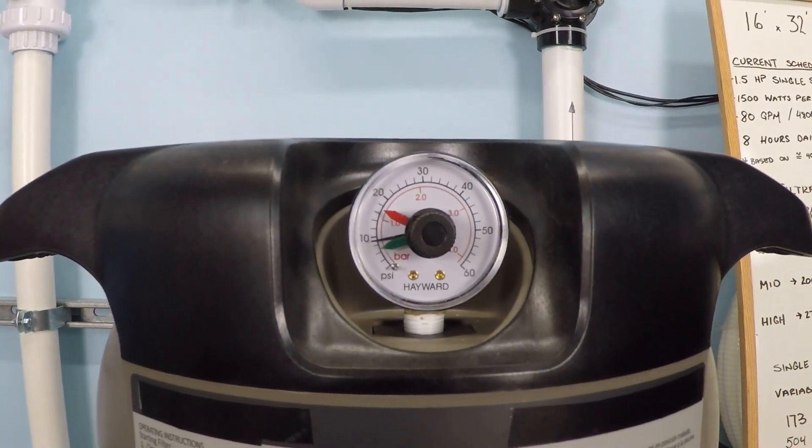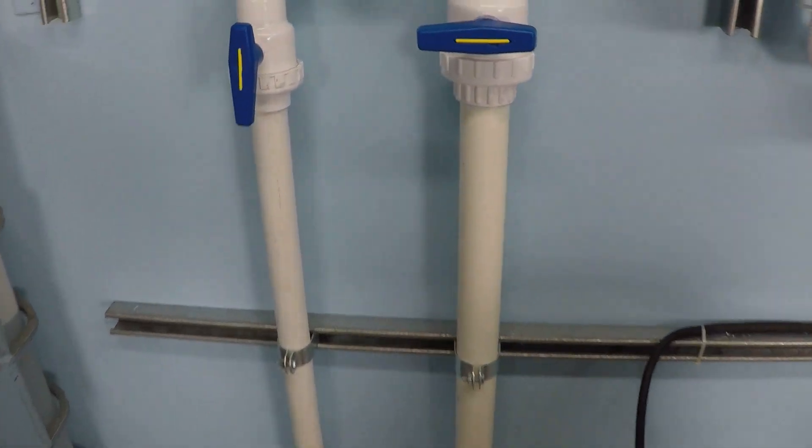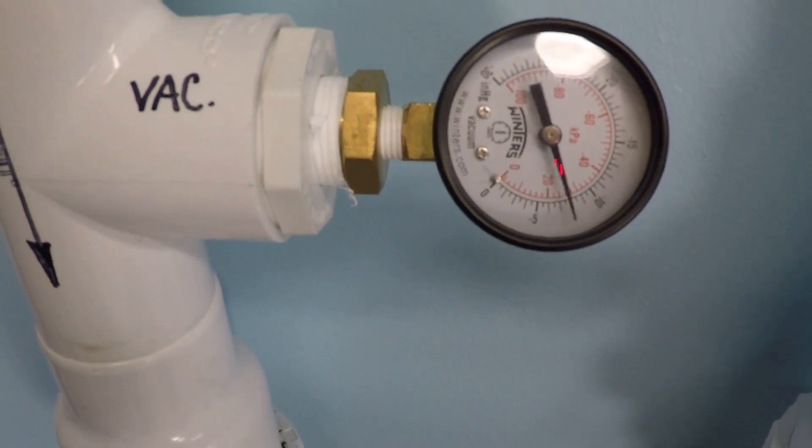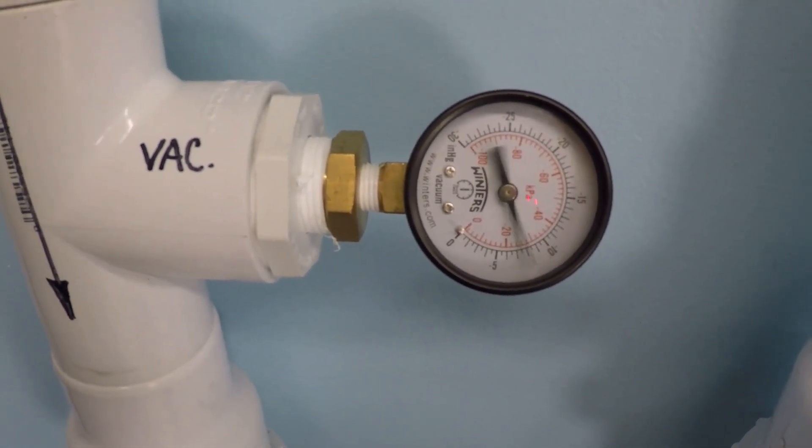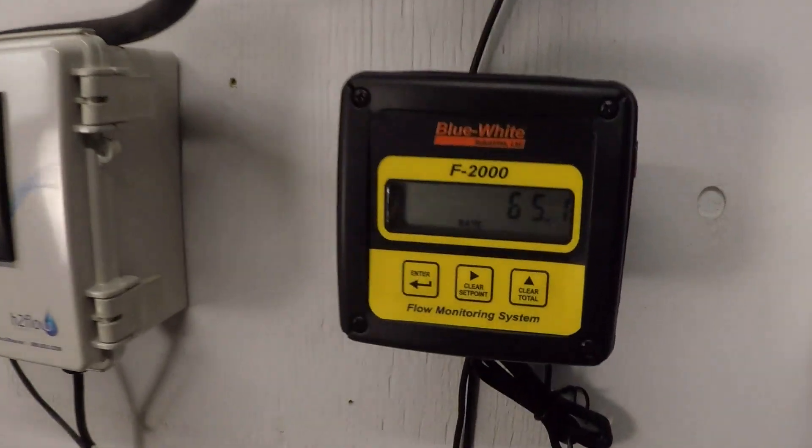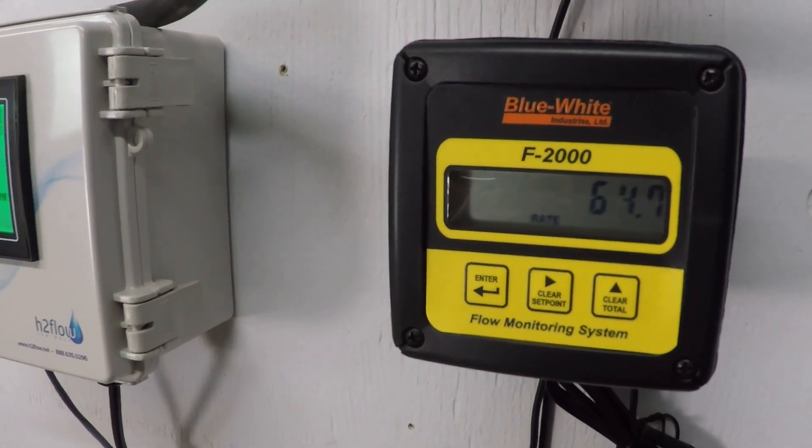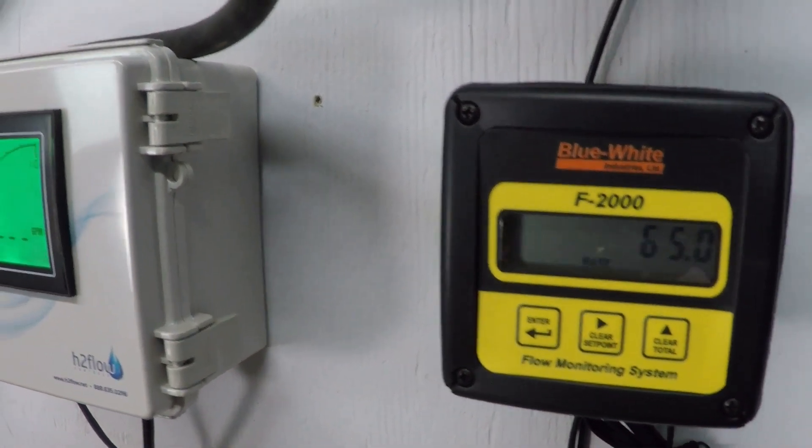It's about 9.5 PSI. We have a vacuum gauge installed here. That's obviously some fluctuations there, but that's about 7.5 inches of mercury. Getting back to the flow rate here, 65 gallons per minute is what we're looking for. It's just about there, 65.